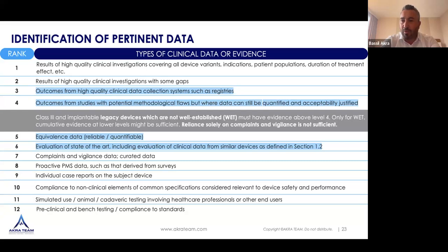So you have a lot of situations. We discussed everything back and forth, and then we came to the agreement. If you have a heart valve or you have a hip implant, without having clinical data of good quality, it will not be acceptable or justifiable to allow such a device moving from directive to the regulation. So we said, you need to have rank 1 to rank 4 data as a minimum to be able to move such a device to the market. But we said as well, if you have a guide wire or a cannula or a catheter, which belong to a class 3 or an implantable classification, and they are a legacy product, but they are, let's say, well established, then it is not an obligation to have rank 1 to rank 4 data.